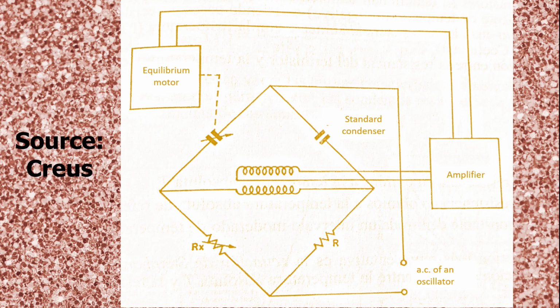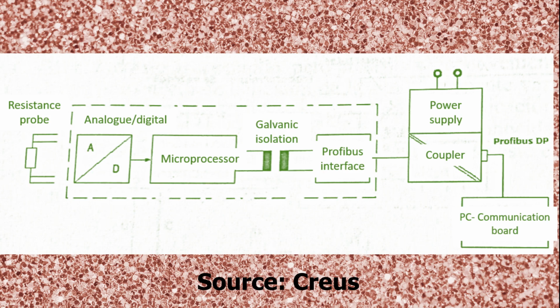Another way to measure temperature automatically is through a capacity bridge, which uses a variable capacitor whose position is calibrated according to the temperature, fitting the circuit with the stabilized alternating voltage of an oscillator. It is similar to the Wheatstone bridge in that, in the event of an error signal, the amplifier feeds the balance motor that drives the variable capacitor. Adding a converter or transducer with data transmission via bus to the resistance probe allows to obtain an intelligent transmitter with the possibility of automatic change of the sensor or the measuring field, obtaining Wheatstone or capacity bridges of different characteristics by hardware or software, etc.